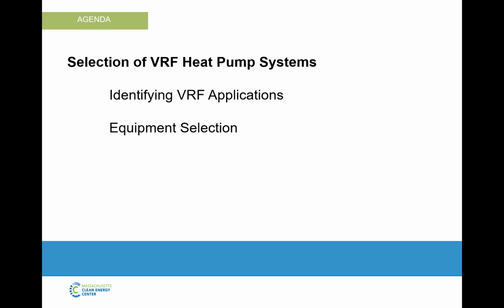But maintenance-wise, any piece of mechanical equipment needs maintenance. Anyone who says that these systems don't require maintenance is lying to you, and you're going to be upset with them in a few years after you don't do any. The beauty of these systems is that the maintenance required is less than conventional pieces of equipment. With a VRF system, the main things you need to do are keep filters clean, especially on these ductless units where they're not meant for high static pressure, they're not meant to push through dirty filters. Keep the coils clean.